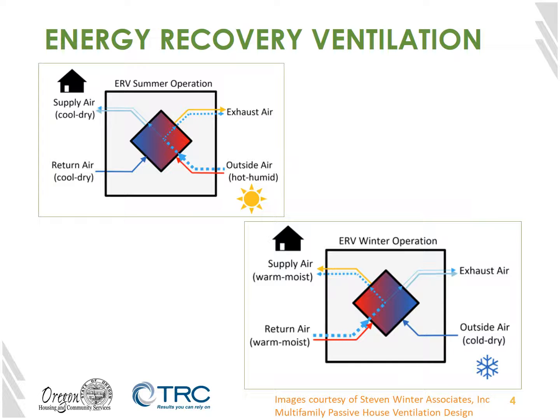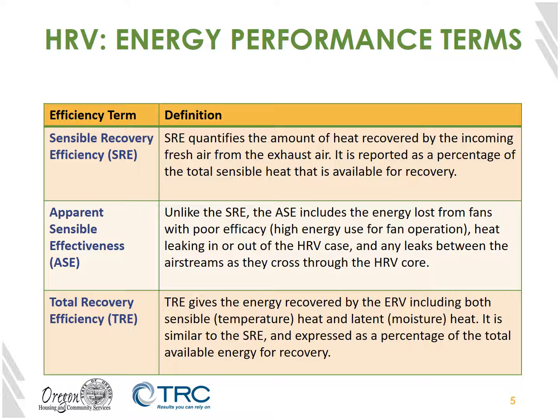At this point in time, we'll talk a little bit about some of the energy performance terms we associate with these devices. We'll start with sensible recovery efficiency, or SRE. The SRE is a percent of the recovered sensible heat compared to the total available heat. For instance, if an HRV has an SRE of 55% for a given flow rate and temperature difference, this means that the HRV core transfers about 55% of the available sensible heat in the outgoing air to the incoming stream.